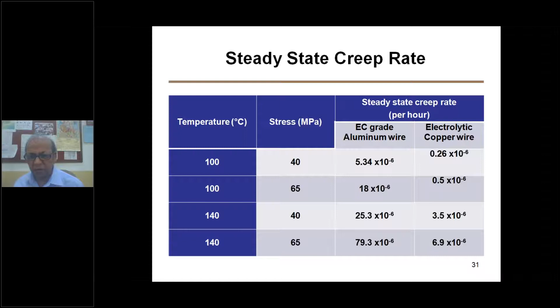So this is again the same thing, that loosening is happening because of this creep, as we explained earlier, so there is no point in repeating. But one point we make here also: the spacing of the radial spacers is very important, and they must be equi-spaced. When they are equi-spaced, you get the best result. If they are not equi-spaced because of poor workmanship, then wherever the space is more, failure will occur from that particular state.